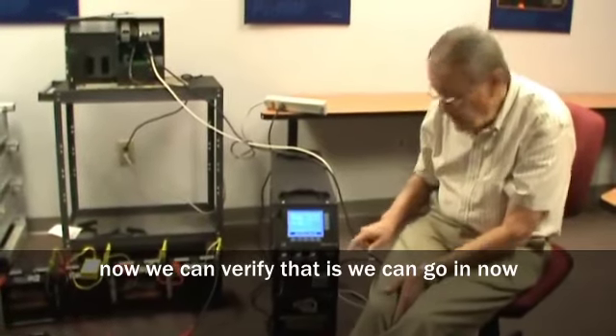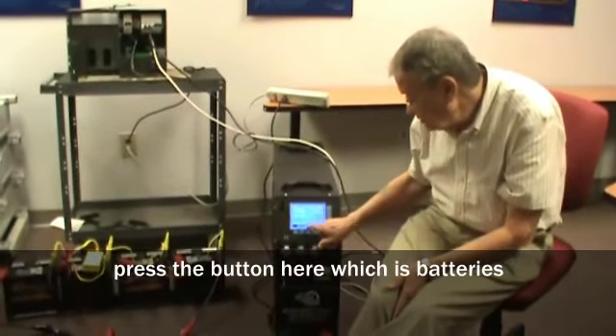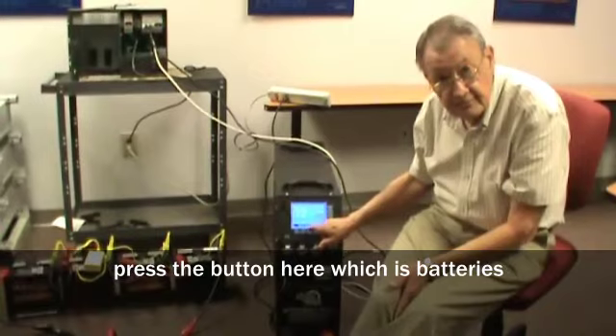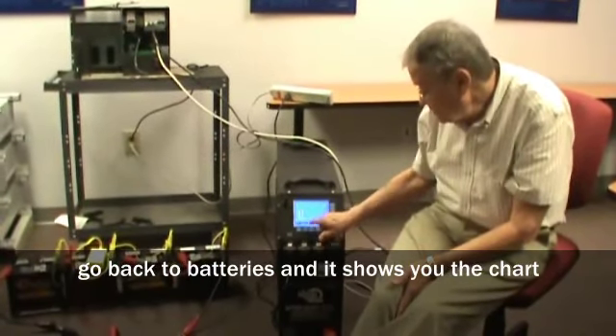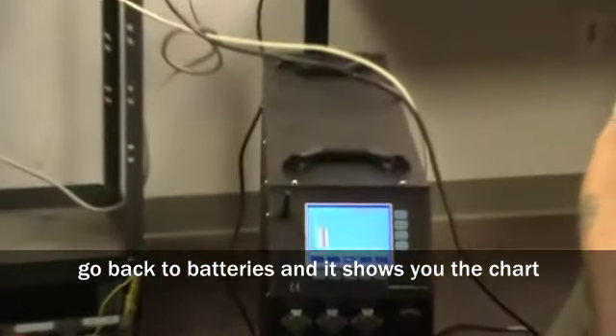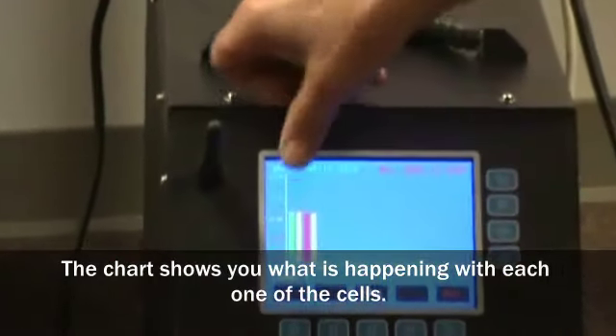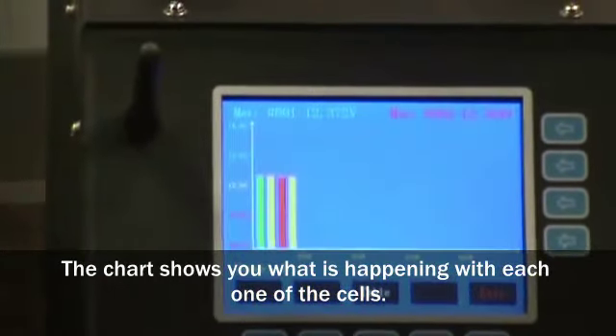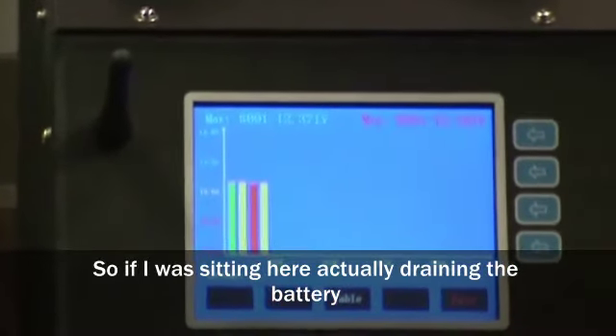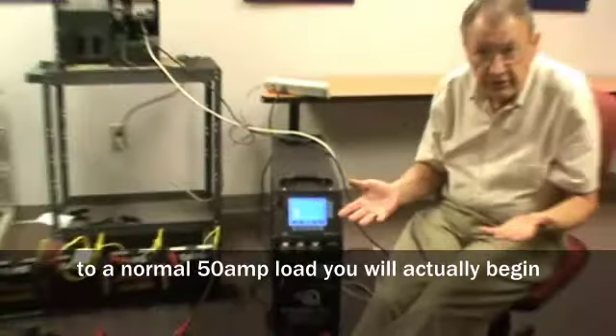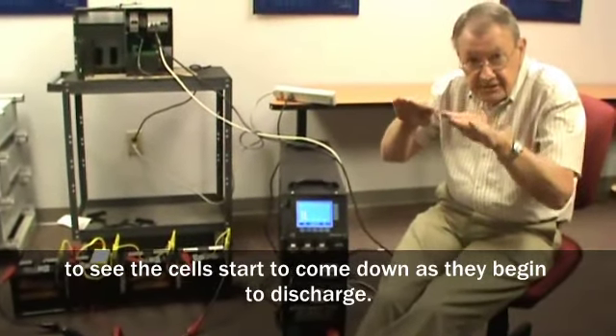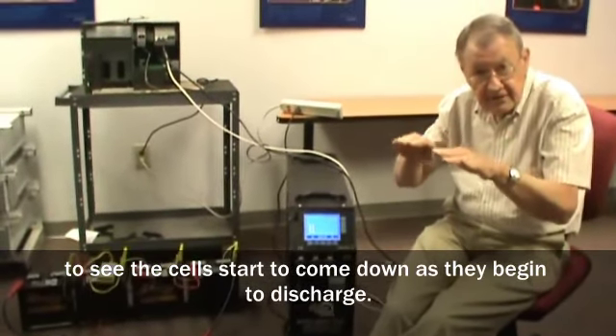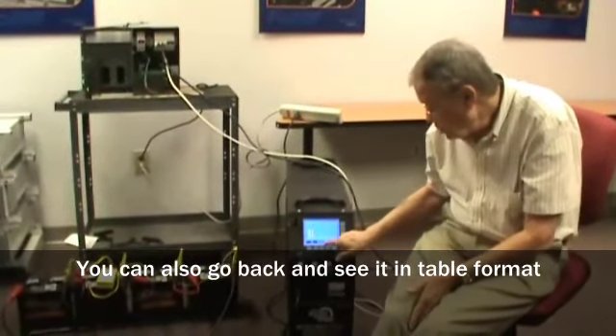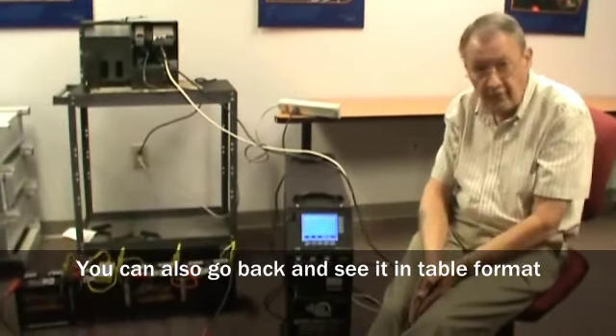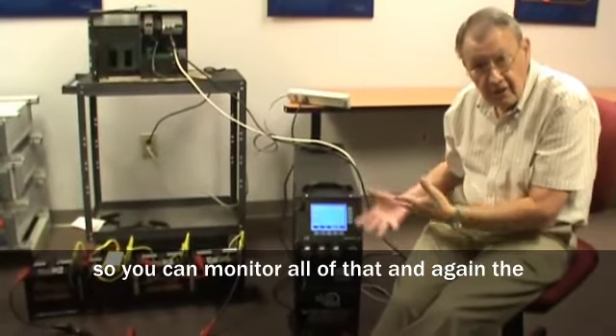Now we can verify that. We can go in and press the button here that says battery. Go back to battery and it shows you the chart. And the chart is showing you what's happening in each one of the cells. So if I was sitting here actually draining the batteries at a normal, like a 50 amp load, you would actually begin to see the cells start to come down as they begin to discharge. You can also go back and look at it in table format. So you can monitor all of that.